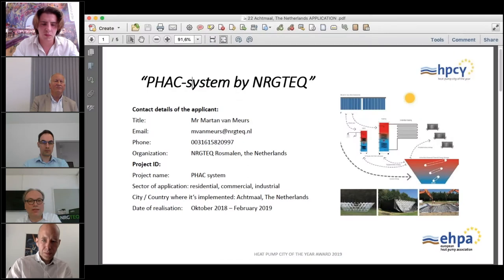In summertime, we run the heat pump on the electricity produced by the PV panels. And if there's no source available, there's no need for cooling the building, then we use the energy provided by the thermal panels from the roof. So we can provide cooling for the building and run the heat pump on the electricity produced by the PV panels. Of course, our waste product, so to speak, is heat, and we need to store this heat in a thermal storage. There are heat pipes or PVT panels providing the energy for the whole system.